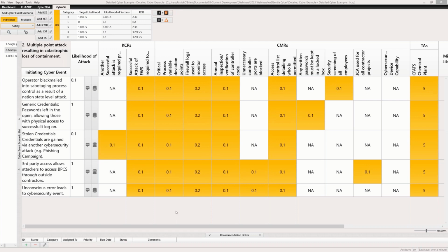And so again, this is something where we don't have hard numbers. We don't have the data yet for cybersecurity incidents and the effectiveness of different protections to know for certainty that a firewall is good for 90% effectiveness or only 80% effectiveness or 50% effectiveness against different attack types. So these are really just order of magnitude estimates, but they provide a starting point for us if we try to get a comparison of how likely a negative cyber outcome may be compared to other, just hardware failures in the control system leading to process excursions or safety impacts.